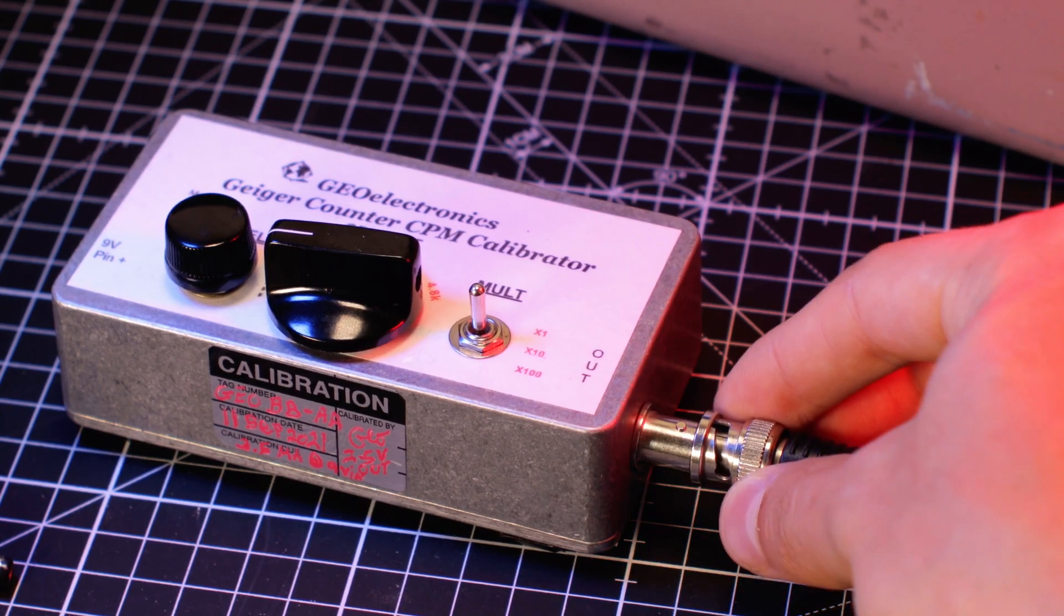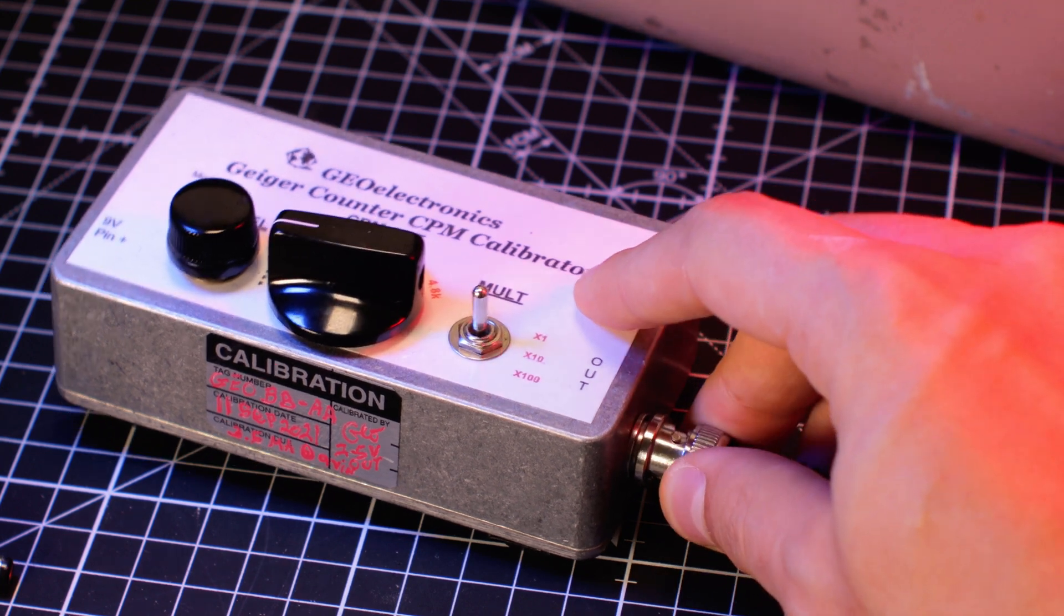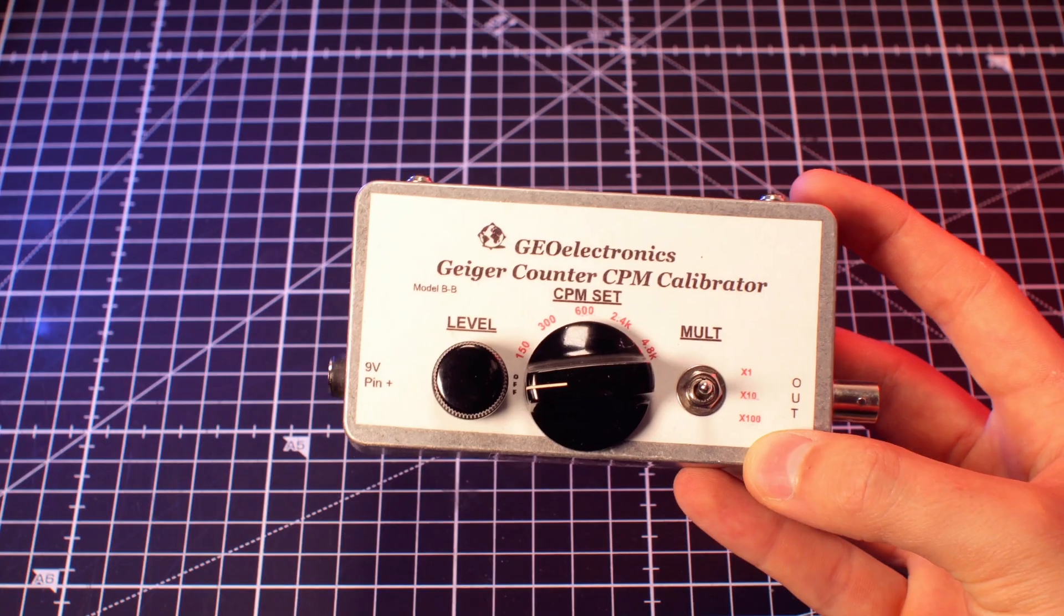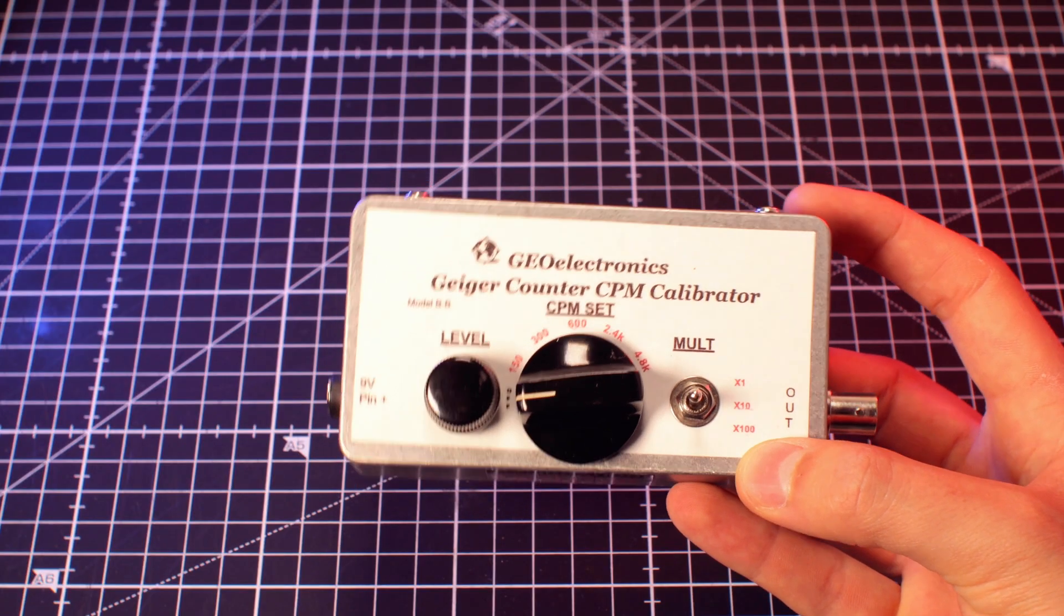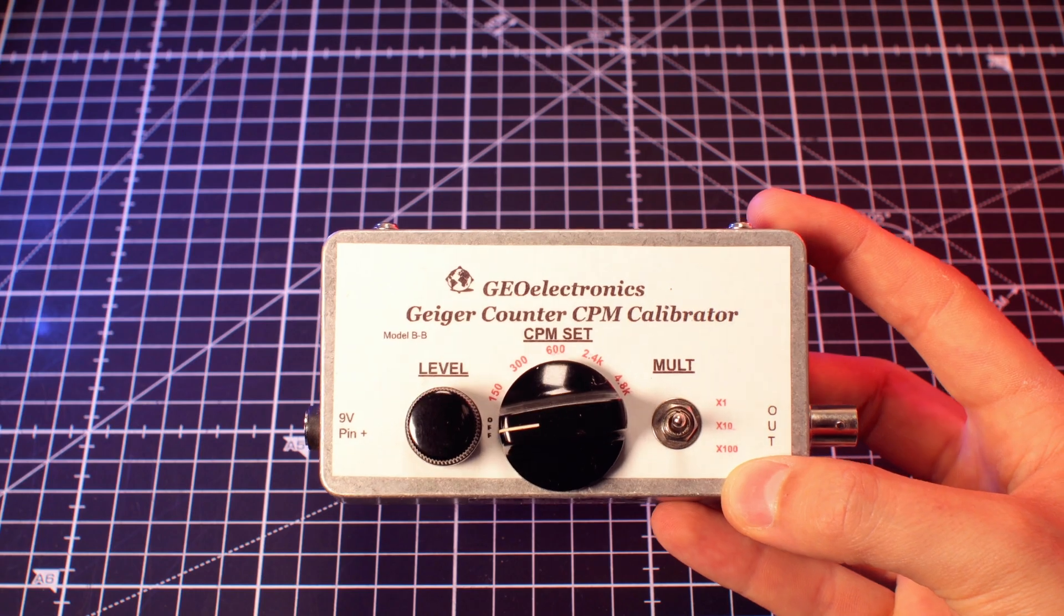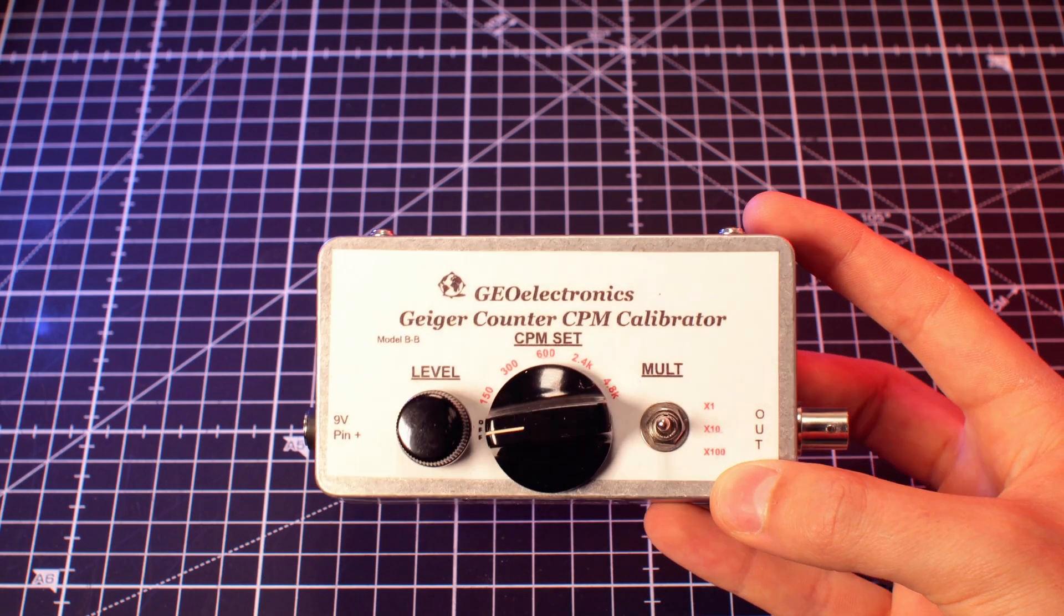The next step is to connect the pulser to the Geiger counter. A pulser will generate clicks at a consistent rate, which will allow us to calibrate the meter.